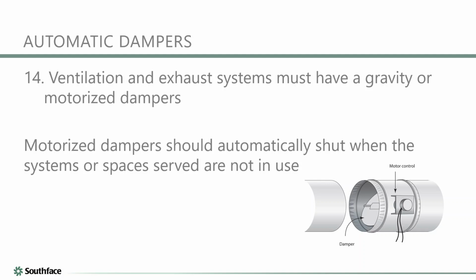All right, automatic dampers here. The requirement here for 14 is saying that your damper has to be either a gravity type damper or a motorized damper. More often than not, what I'm seeing in the industry is neither motorized nor gravity, right? It's usually the cheaper ones that you balance by hand. So now this is a new requirement that's going to probably add cost to your project, but it is the law of the land, and that's where we have to go right now.